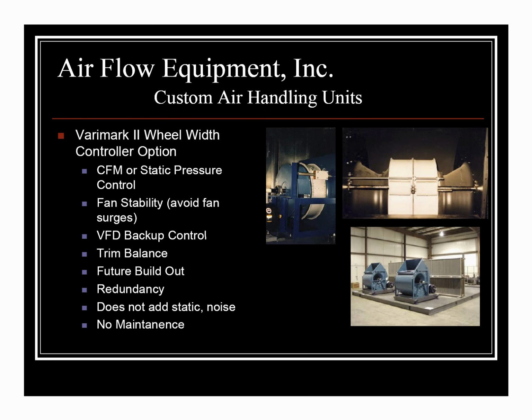We would use this in a couple situations, obviously, in the type of situation where you've got a larger future CFM, but a smaller initial load. If you design with a big fan and you have a smaller initial load, you need to keep your tip speed on the fan up to maintain static pressure. And sometimes that's obviously just not doable with a big fan. As you begin to slow it down, you lose your ability to create static pressure.